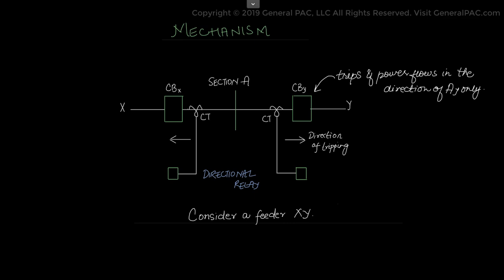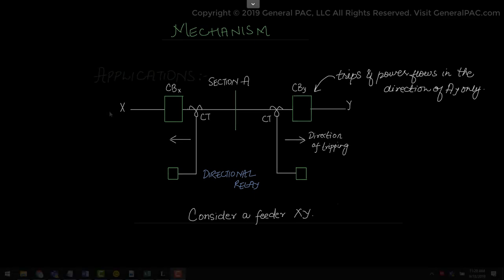However, for fault in feeder AY, then CBY should trip because the fault is in the direction of the relay and it's in the direction of AY.